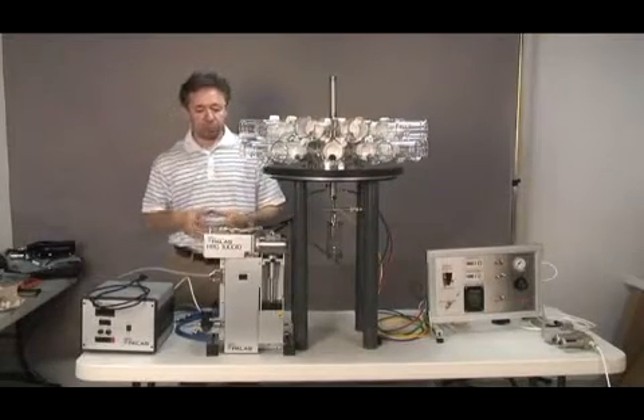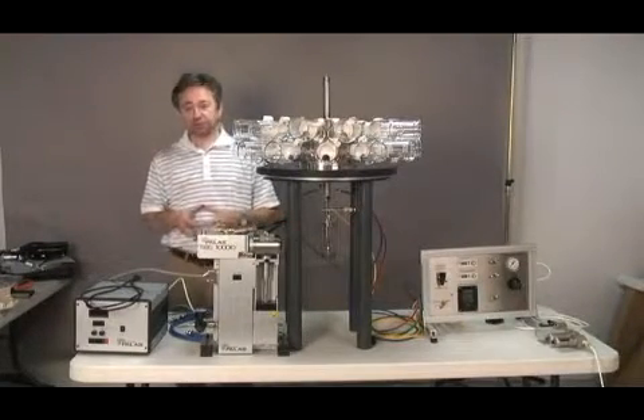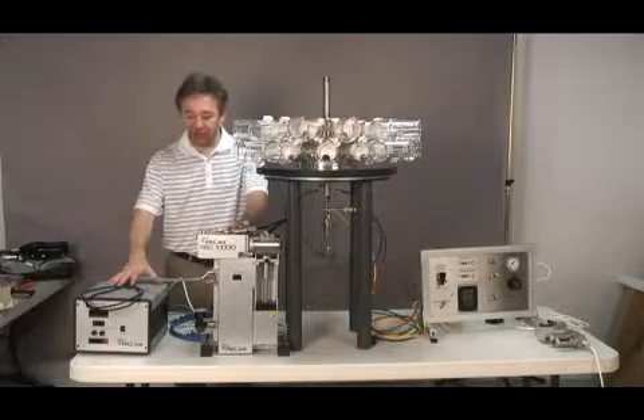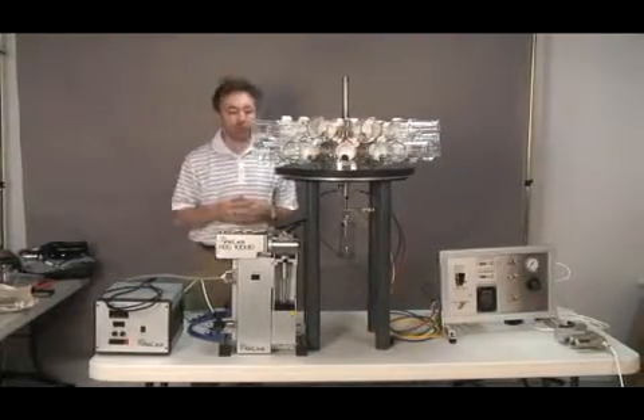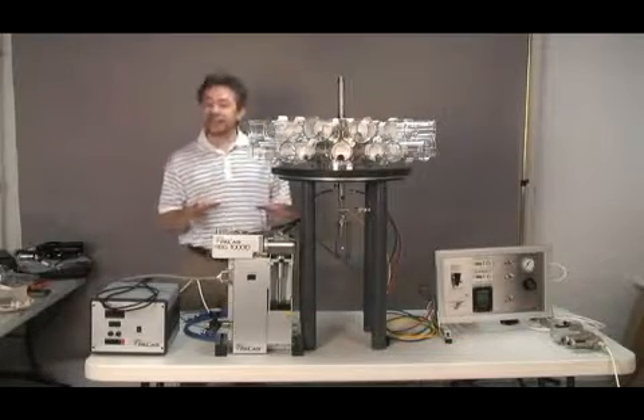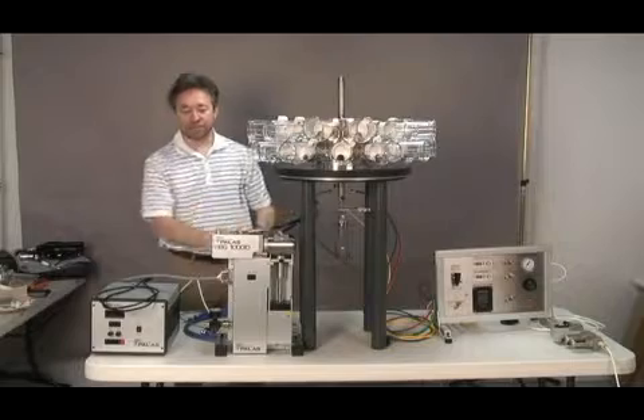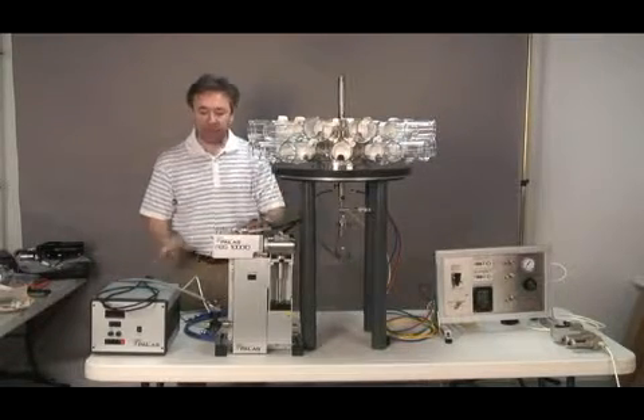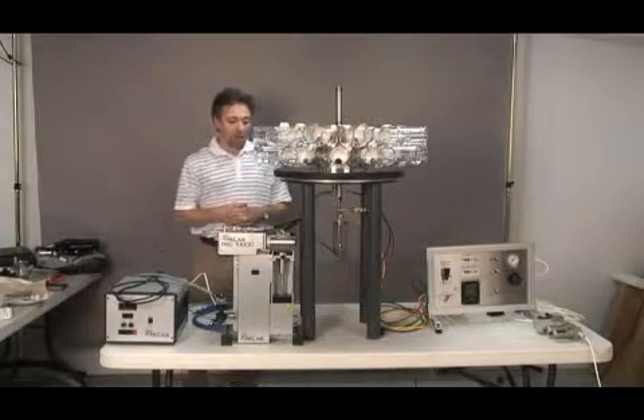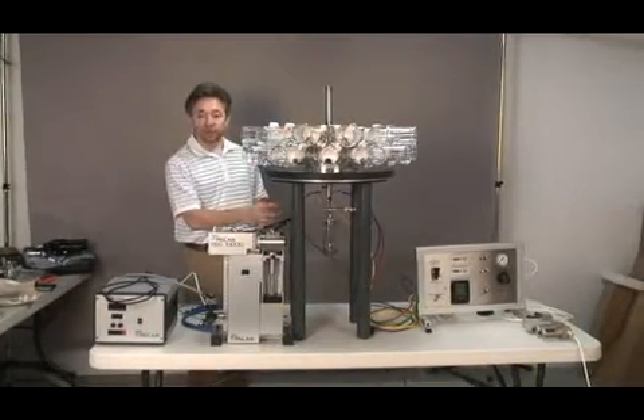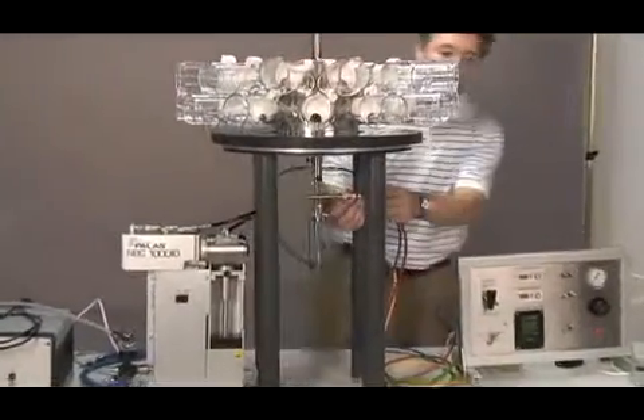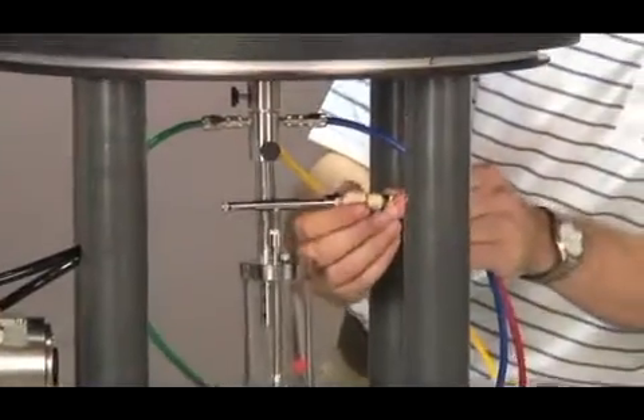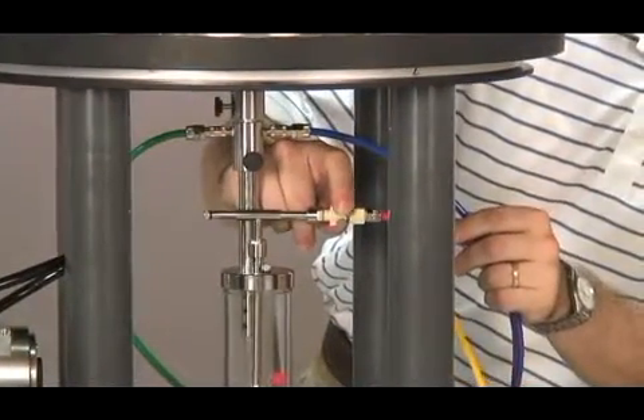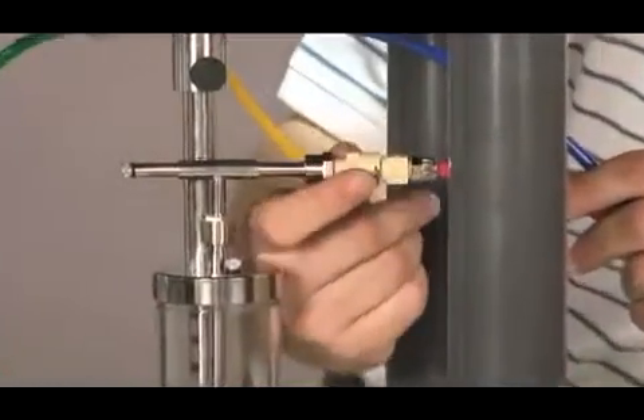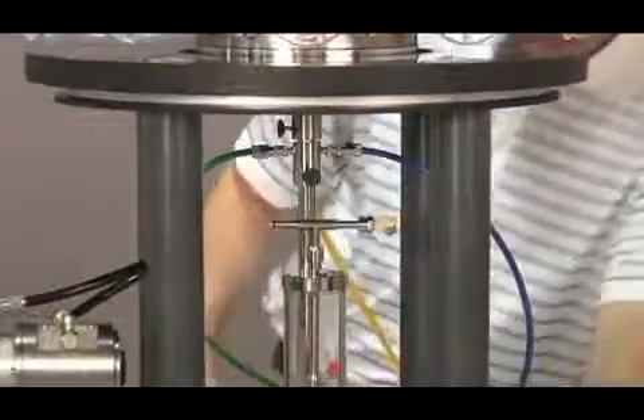If you have to do exposures with powders, the RBG, rotating brush generator, is the dust dispenser that you're going to use. It is relatively easy to switch from a liquid nebulizer to the RBG because all the connectors are compatible with the tower. We start by removing the Collison nebulizer. First of all, remove the air line going into the nebulizer. The way it's done is click into this little metal tab, push it, and then the connector will just pop out.